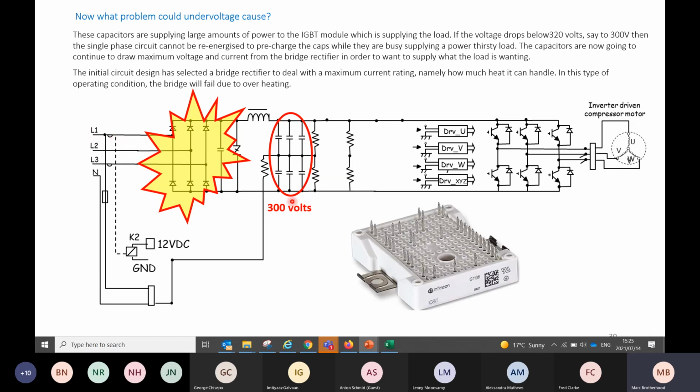Okay. And this is technically another fancy design. A lot of manufacturers are using these. These are about 1,400 Rand each, this little thing. What this does, it has all these 6 thyristors built into it, as well as these 6 diodes. And that is how we miniaturize power electronics. So when that blows, bang, you're going to blow everything, and your whole inverter board goes.